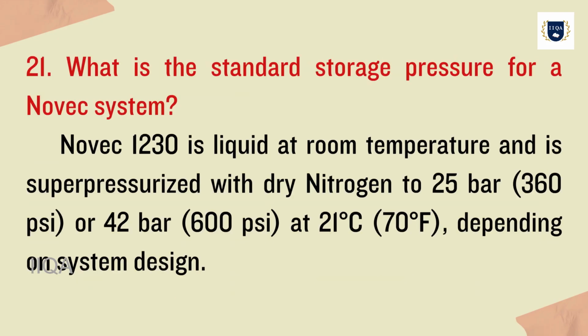21. What is the standard storage pressure for a Novec system? Novec 1230 is liquid at room temperature and is superpressurized with dry nitrogen to 25 bar, 360 psi, or 42 bar, 600 psi, at 21 degrees Celsius, 70 degrees Fahrenheit, depending on system design.